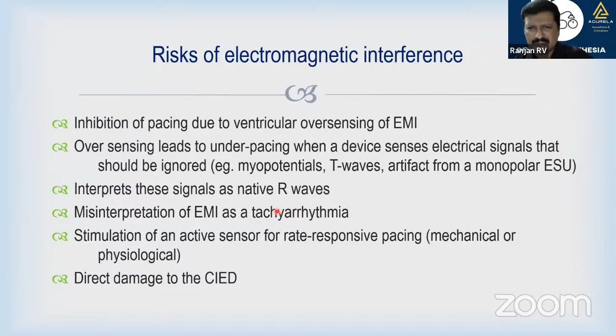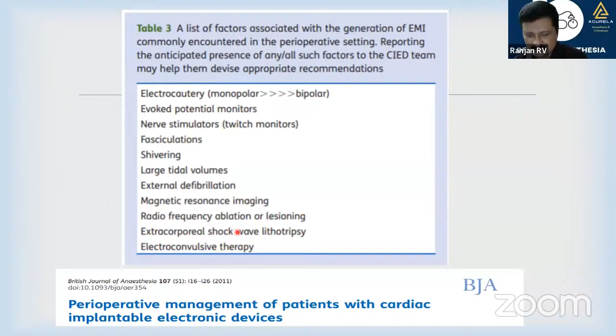So what are the factors which cause EMI? The most common one is the electrocautery, monopolar more than the bipolar, evoked potential monitors, nerve stimulators. Okay, we will come to that. Fasciculations caused by succinylcholine can cause an EMI. Shivering, large tidal volume. If your fourth letter, that rate modulation, is on, then the large tidal volumes can cause a problem with the pacing. It acts as an EMI. External defibrillator, MRI, radiofrequency ablation, ESWL, ECT, all this can cause EMI.